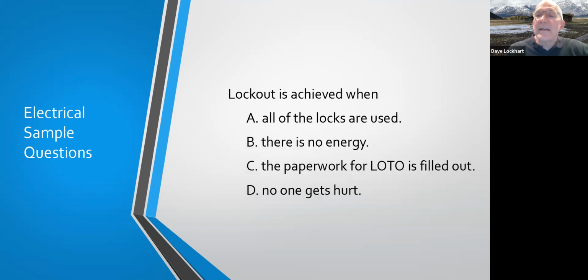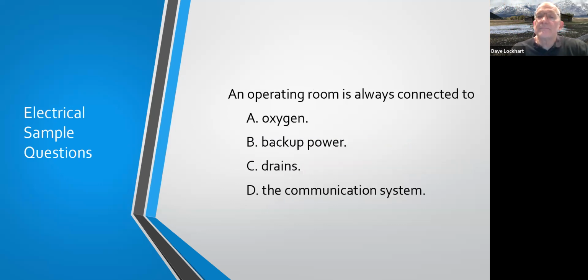All right, lockout is achieved when, okay, so using a lockout tagout, so this is safety. A, all of the locks are used. B, there is no energy. C, the paperwork for a lockout tagout is filled out. D, no one gets hurt. Yes, B is the correct answer. There is no energy. Again, having the paperwork filled out is good, but that doesn't mean that the energy is secured and everything is taken care of. And I do like that answer as well, that no job is done until the paperwork is completed. So you definitely want to have your lockout tagout paperwork completed so people know you've applied it and what you've done. But basically, there's no energy. We want to protect those working on the circuit.